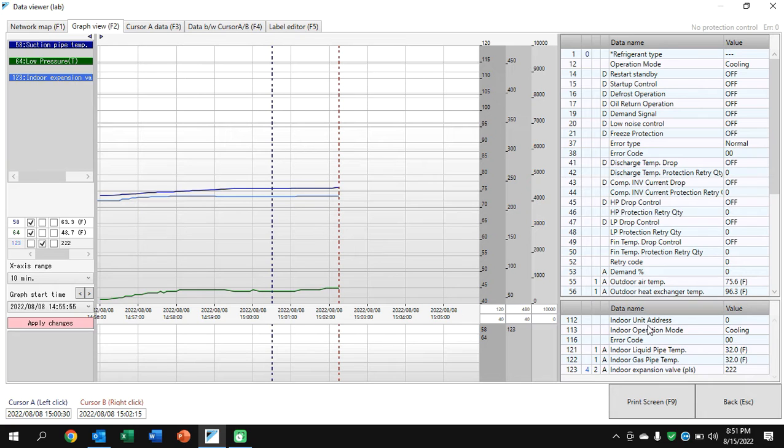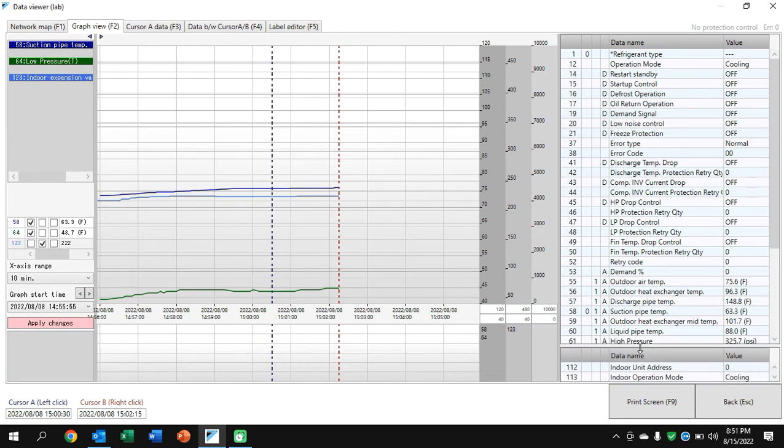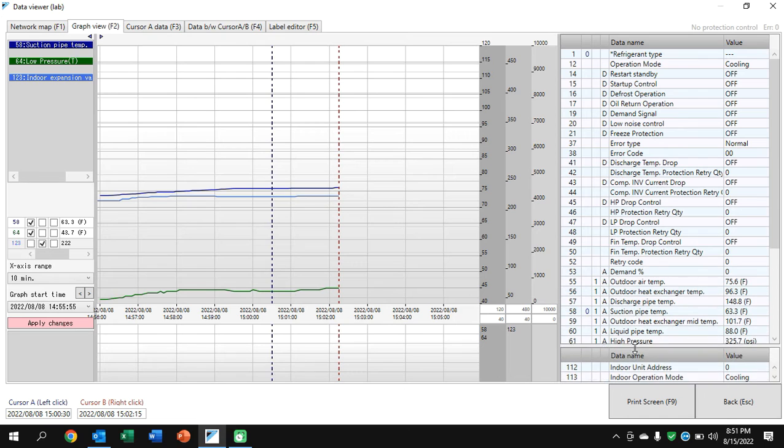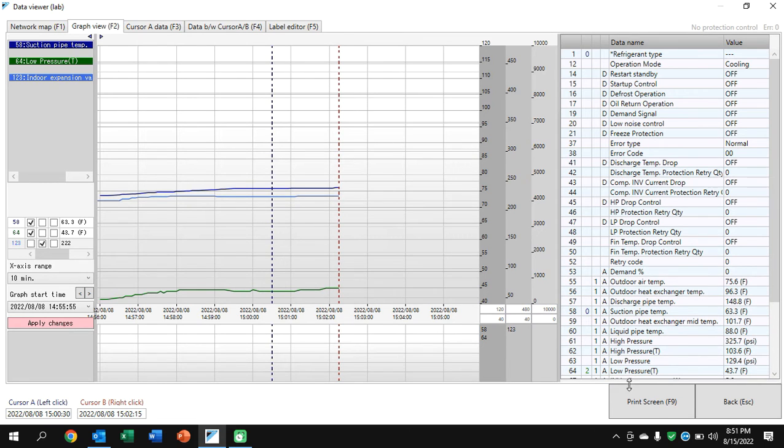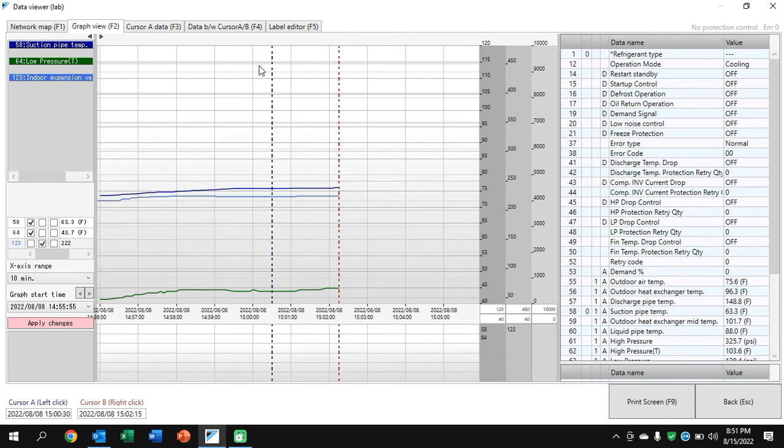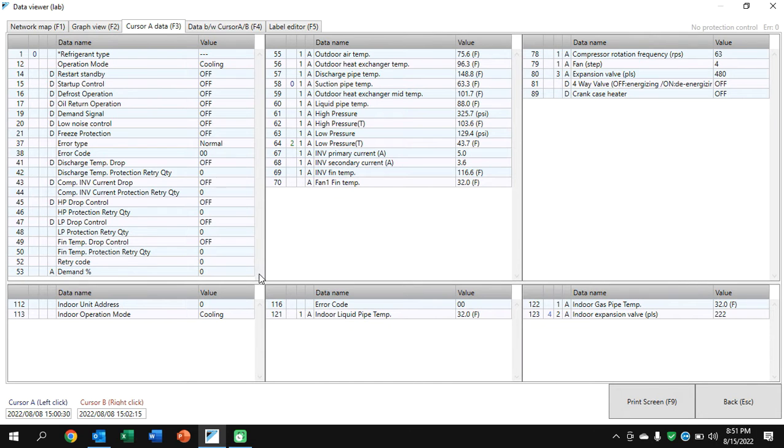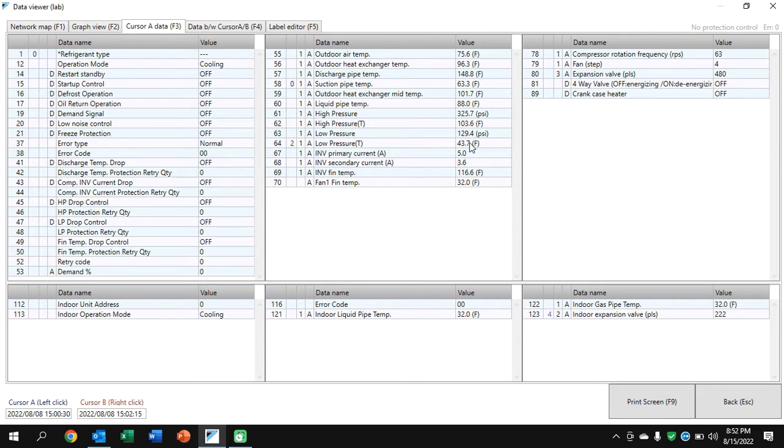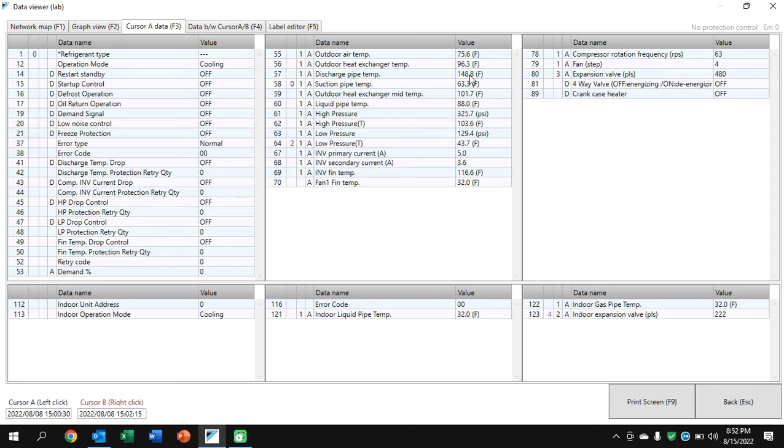You can see here I updated it. I added my EV pulses. I want to watch my EV. On this fit unit, indoor coils, 480. Most are 480 or many splits are 470 or 480. This one is going to be 480. And I'm going to monitor that to make sure I'm staying at generally 50 to 70 percent. So normally, well, I'll see it. And if I see it out of that range, something is occurring I might want to keep an eye on. And you can see the pulses in the down area there at 222. So I'm a little under half. And this is my lab unit. It's quite cool inside the room. It's kind of to be expected, the data I'm getting to show here. Very small line set and cool inside.